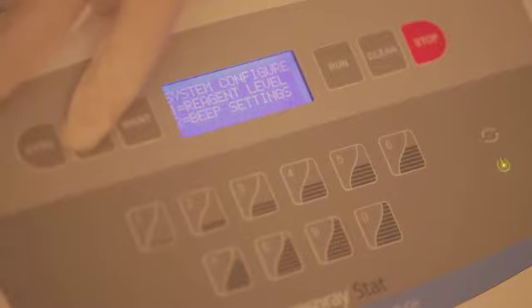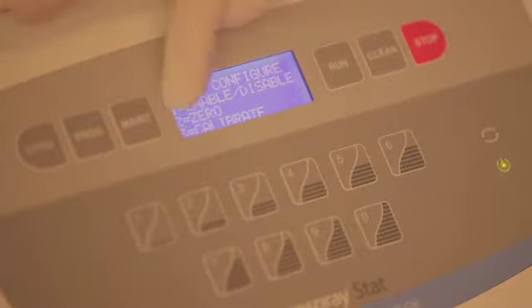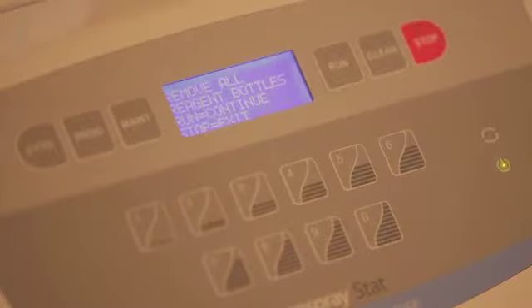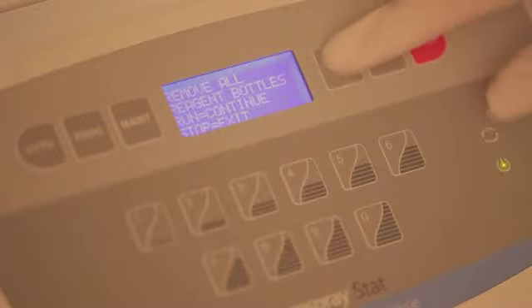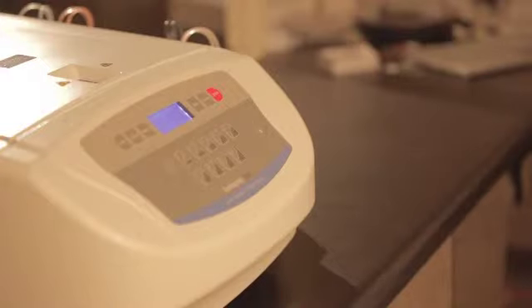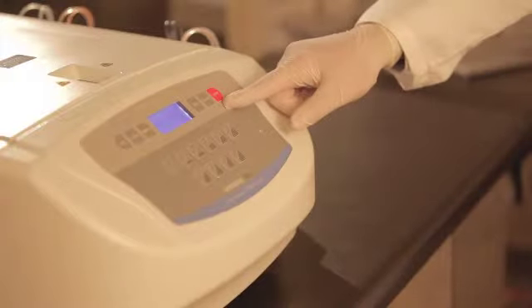While it is rebooting, press the Program button. A screen will appear that states 1 level sense, 2 beep settings. Press the number 1. Options for 1 are 1 Enable/Disable, 2 Zero, and 3 Calibrate. Press 2 to zero. Instructions to remove the dip tubes from touching the sensors appear on the screen. Press Run to begin the zeroing process. This takes approximately 10 seconds. When completed, press Stop twice to return to the main screen.